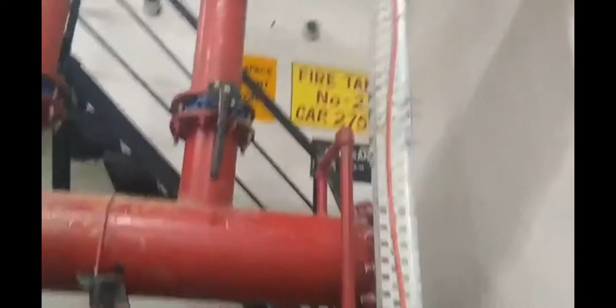In the sprinkler system, there is one pressure switch and one pressure gauge. The cut-on pressure and cut-off pressure have been mentioned. This is automatically on but manually off as per NBC. The cut-off pressure mentioned for the sprinkler pump is 7 kg.